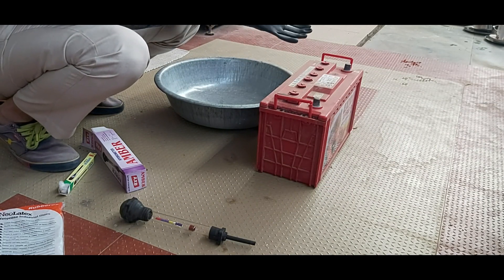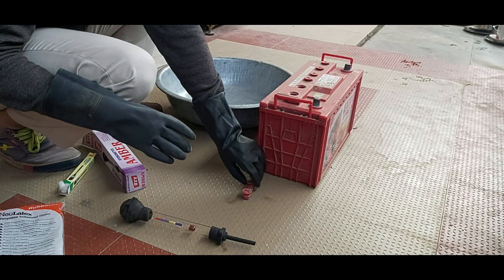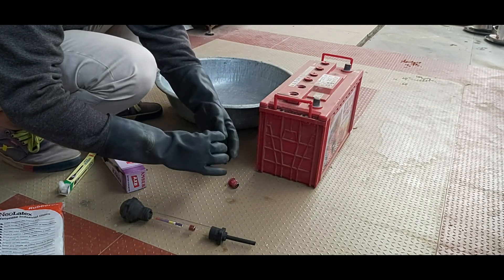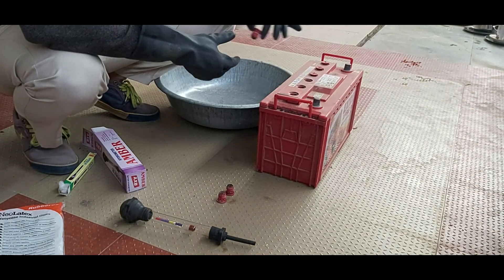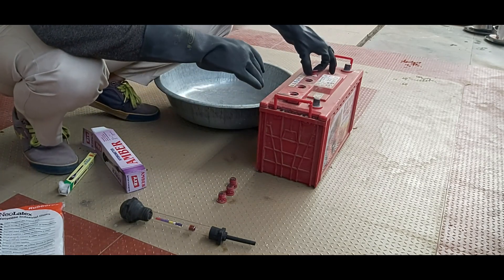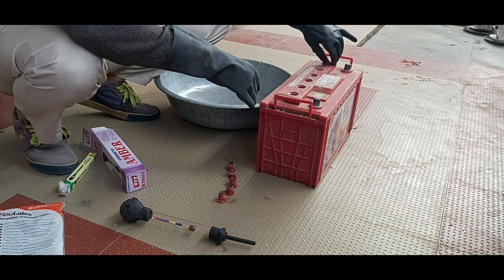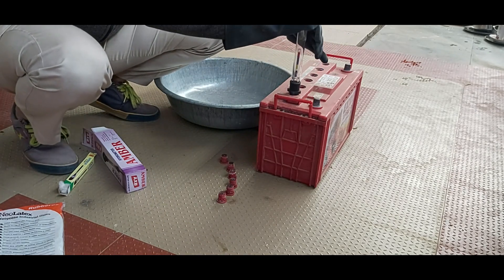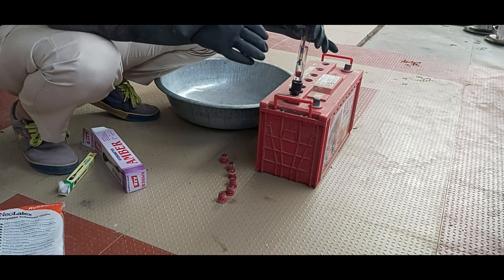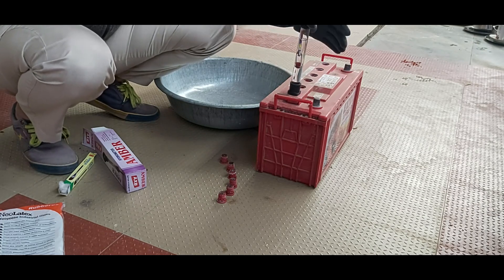Make sure all your PPE is on and you take care of your legs and hands while working with batteries. In order to test the specific gravity, you need to dip the hydrometer into the cell and pull the liquid out into the hydrometer. The float inside the hydrometer will indicate the specific gravity. If it is above the water level marker and reads 1.250 or above, then it is a good cell.